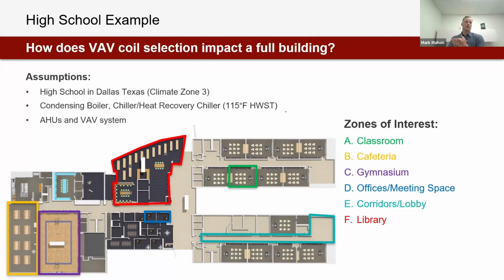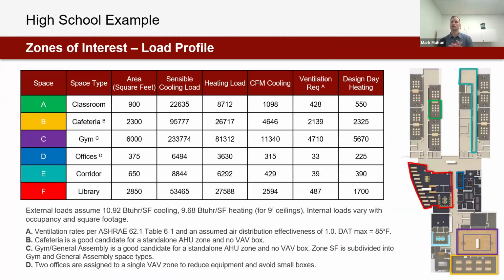So my assumption is a high school in Dallas. It's a classic air handler and VAV system. We have a condensing boiler and a heat recovery chiller. Because of those two things being used in parallel, or actually in series with one another, was my assumption, what we're going to see is a 115-degree hot water supply temperature. So a very lean hot water supply temperature, something that we could see in Dallas that maybe at this point would be less common in Wisconsin just because of the heating load we actually need to provide to the building.